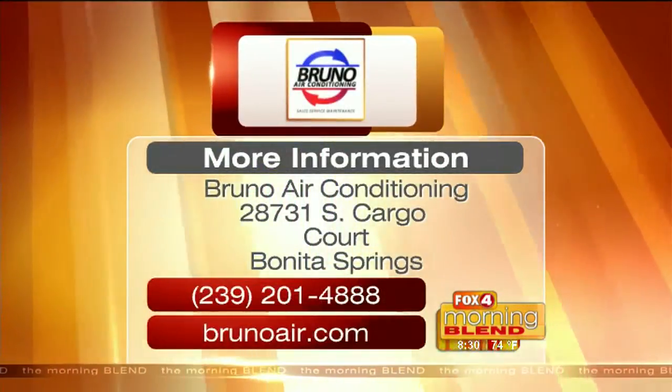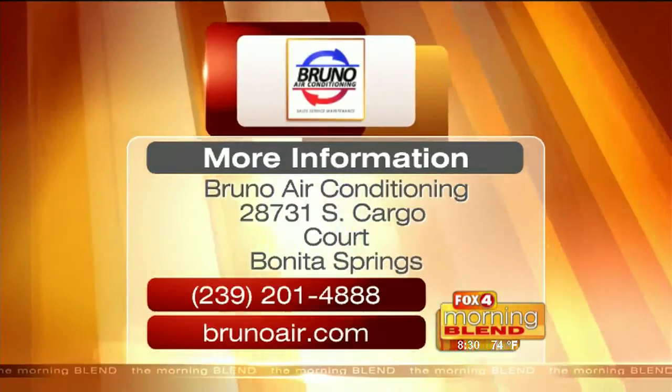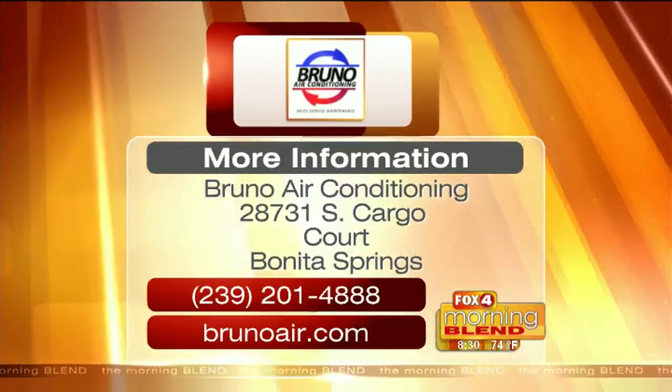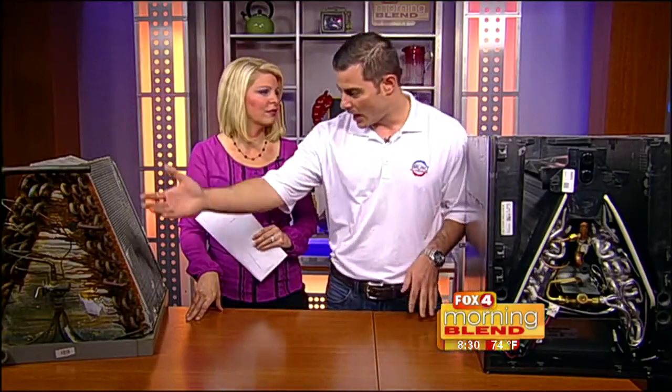So a part of your maintenance is adjusting airflow. A part of your maintenance, when it's done properly, our super tune-ups take 2 hours to do. We take the unit completely apart. We check the duct system. We've got a North American ductwork certification. So with those certifications, we know how to meter airflow, how to check airflow. And when you have hot spots in the home, you've got cool spots in the home, that usually means that there's a duct pressure issue. And when you have a duct pressure issue, it's going to cause excess moisture on the coil. The coil's going to stay wet all the time. It's never going to dry off. Excess moisture leads to poor indoor air quality, leads to high energy bills. It leads to biological growth, mold, fungi.